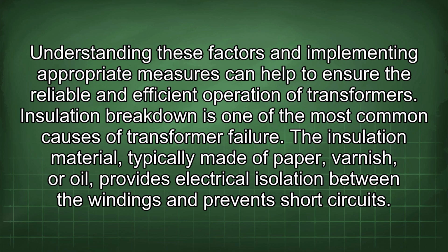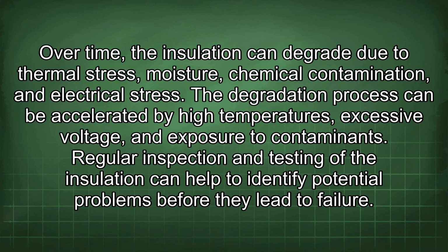Insulation breakdown is one of the most common causes of transformer failure. The insulation material, typically made of paper, varnish, or oil, provides electrical isolation between the windings and prevents short circuits. Over time, the insulation can degrade due to thermal stress, moisture, chemical contamination, and electrical stress. The degradation process can be accelerated by high temperatures, excessive voltage, and exposure to contaminants. Regular inspection and testing of the insulation can help to identify potential problems before they lead to failure.